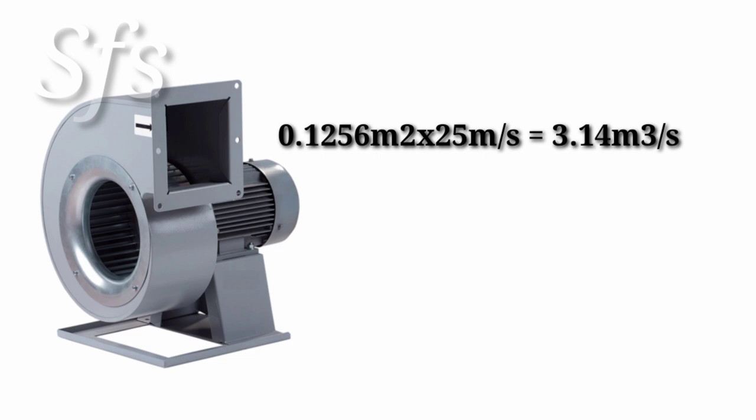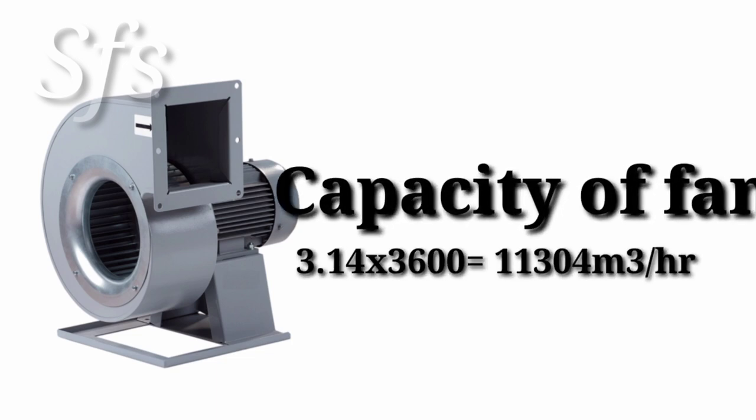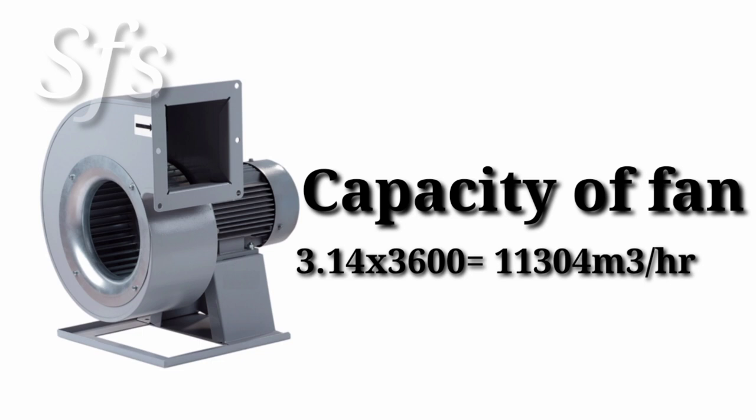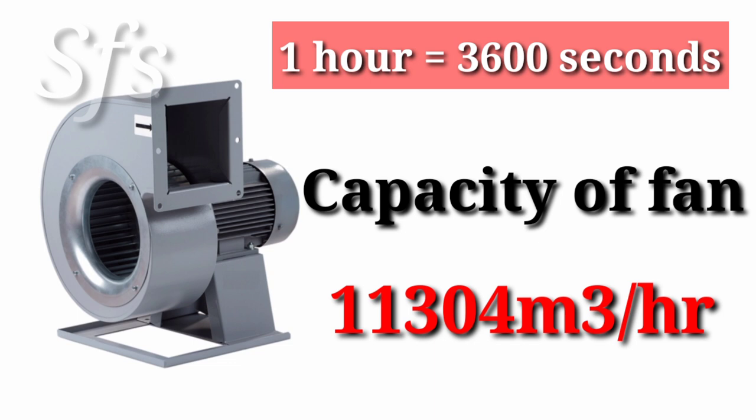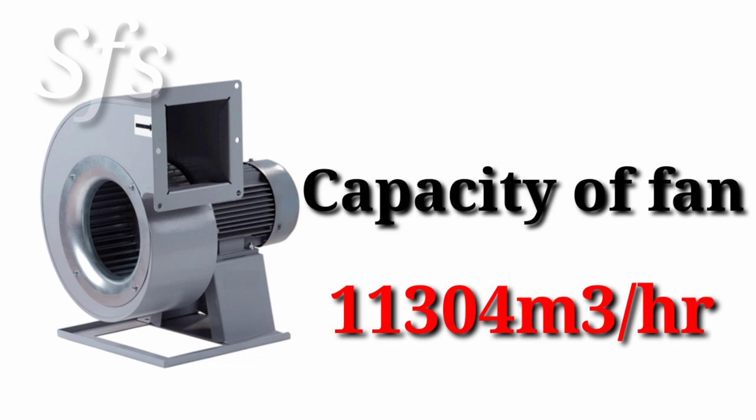To calculate the capacity in meter cube per hour, multiply this value by 3600. So 3.14 multiplied by 3600 equals 11,304 meter cube per hour. Why do we multiply by 3600? Because in one hour there are 3600 seconds. So the capacity of that fan is 11,304 meter cube per hour.